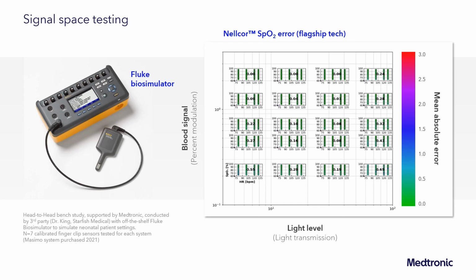And so in this situation, it's a big test where we change SpO2 and heart rate and the light level and percent modulation. And we can test all of these different conditions. What we want to see is that no matter where you're at in that test condition, the Nellcor pulse oximeter is performing very well, and that's what you're seeing here. This is important for both the design as well as the support of released products. So once our pulse oximeter goes out into the market, we want to make sure that you continue to have that high quality performance you've come to expect.